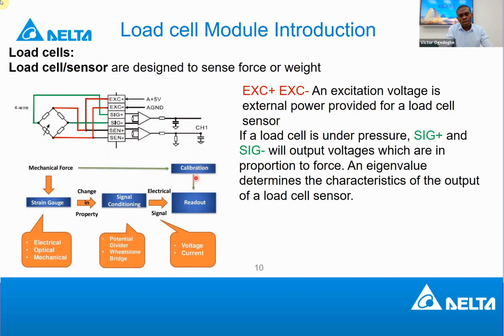And then here is where we get the data into the load cell module. So with the load cell module of AS300, you can calibrate this output to what you want it to be. So you can really manipulate the readouts from the sensor, and then that calibration, you can use it for your application to make your weight application very efficient.